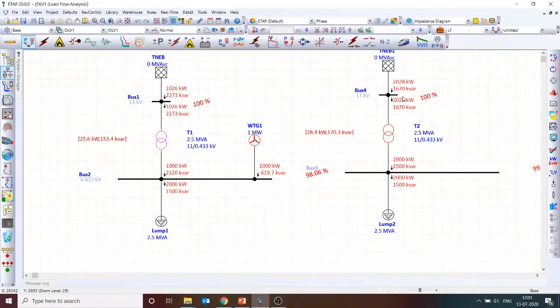So the power which you are consuming from the utility is 2028 kilowatt. That means if your industry runs with this load for 1 hour, then you will be consuming 2028 units. For that, you will be billed. And if it is a commercial building, then 2028 into 8 rupees approximately, you can imagine how much the price. So if your industry is running for 1 hour like this, then your electricity bill will be 16,000 rupees for 1 hour. I am making an approximation with an assumption of commercial, and it is in Tamil Nadu, and the tariff is 8 rupees because you are consuming about 2000 units. 2000 units into 8 rupees, it is 16,000 rupees is what you need to pay to the utility for 1 hour, right?